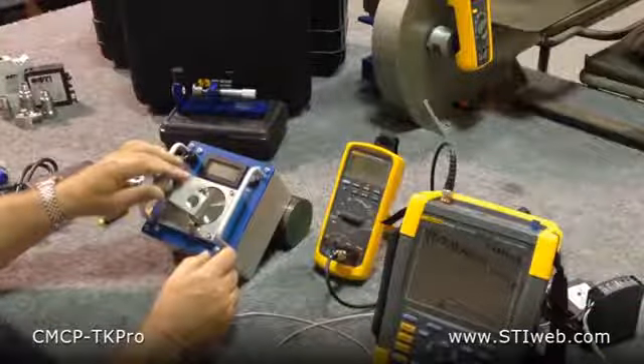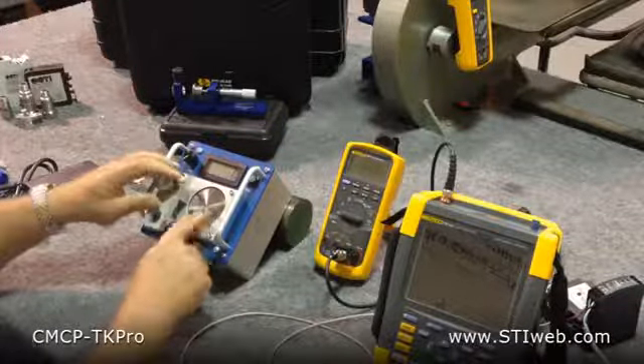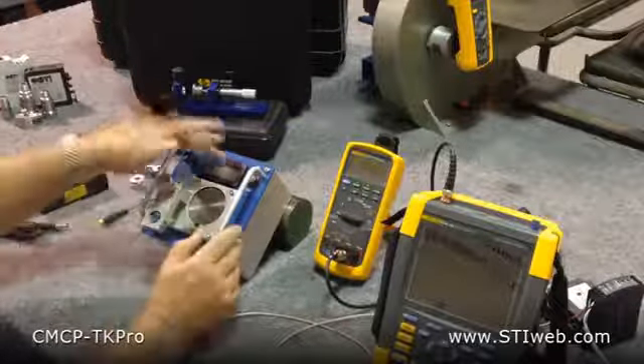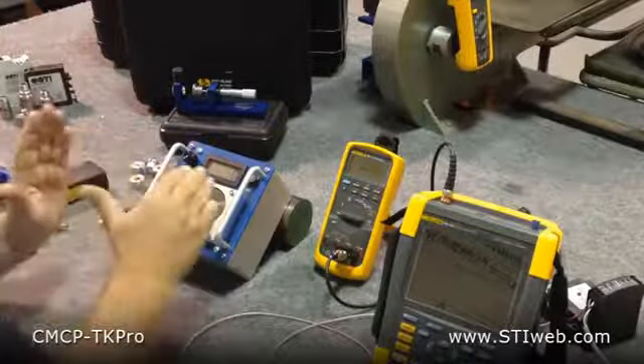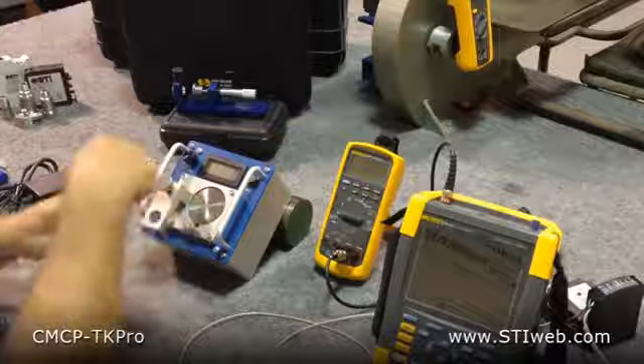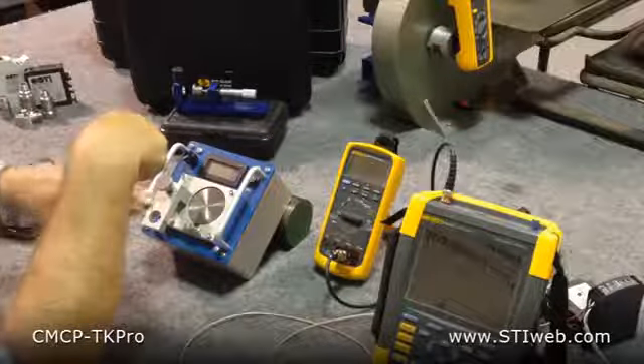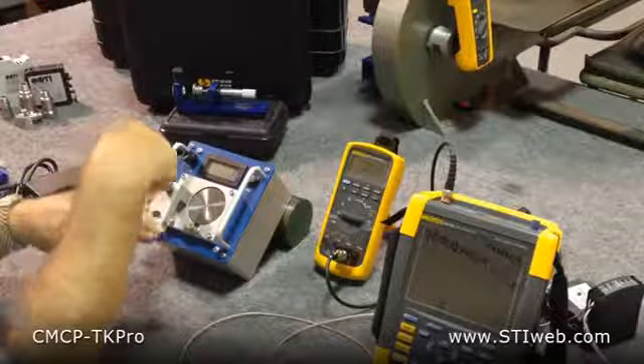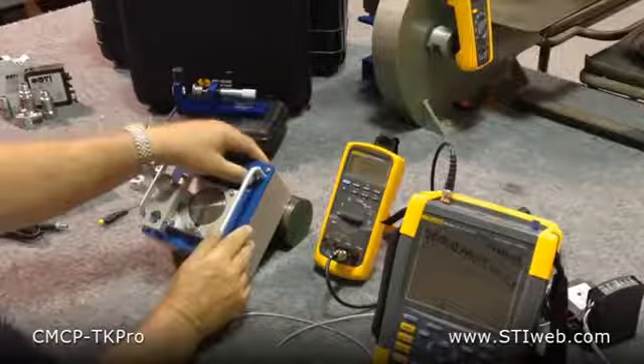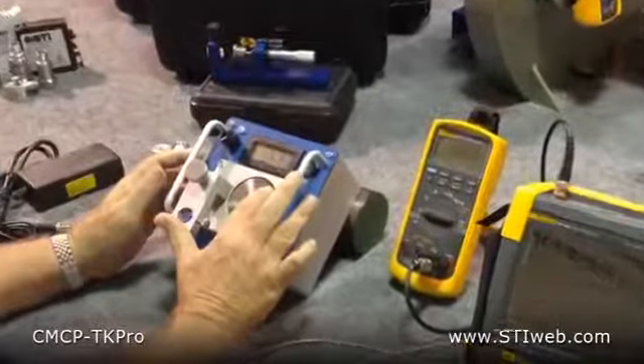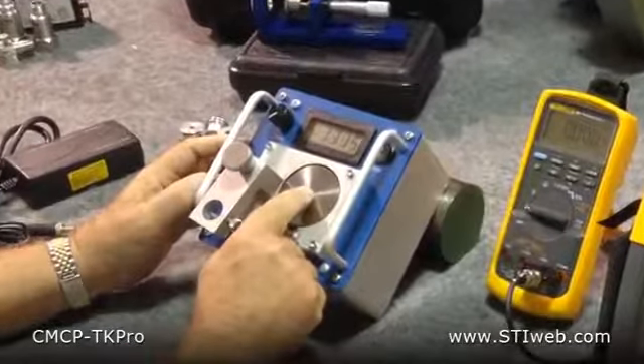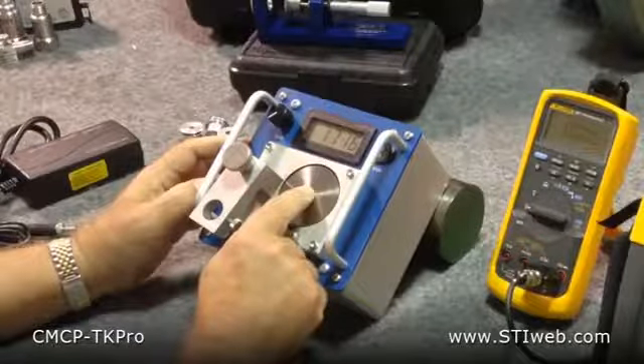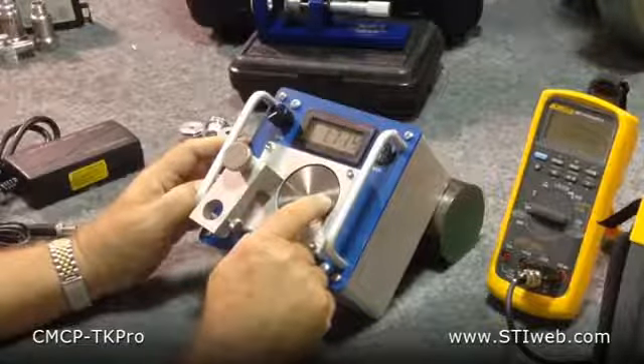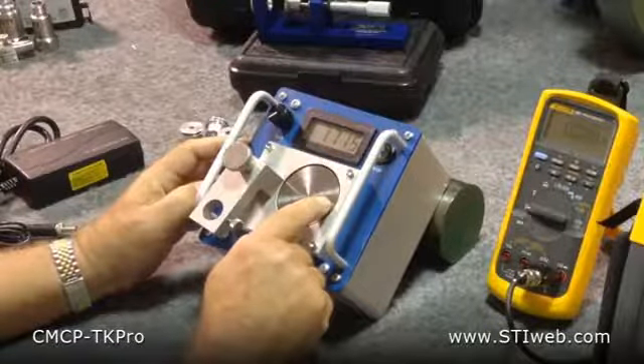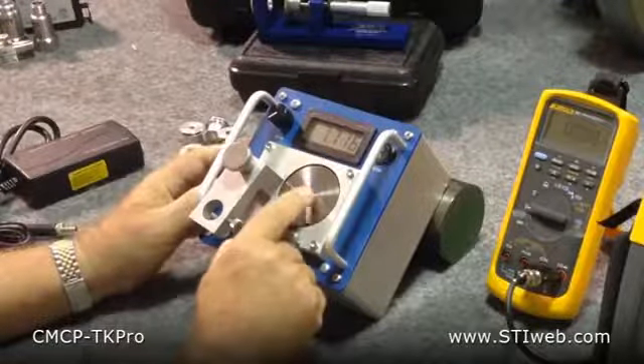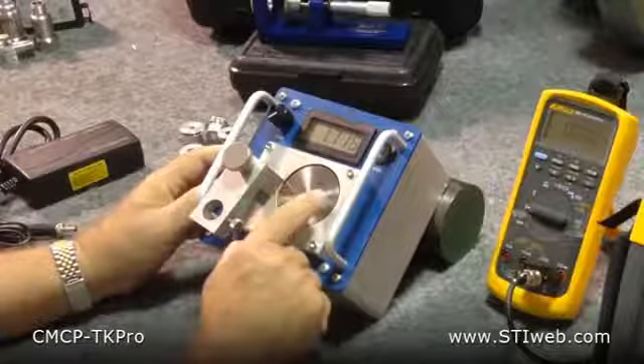Okay, the way the wobble plate works is we have what we call a wobble plate. This is a spinning disc that we can spin at variable RPM, and it's cut at a slant. So if you're looking at the center of the plate, there is no change. But if you're looking at the edge of the plate, it's going high to low. And that's where the term wobble plate comes from. So when I turn this on, you can actually see the plate wobbling. If the proximity probe is looking in the center, you have 0 mils vibration. If you're looking towards the outer edge, you have 15 mils of vibration. So this particular kit will go from 0 to 15 mils of dynamic vibration.